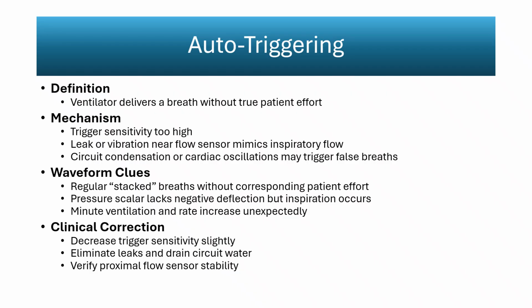Not every irregularity on a ventilator waveform reflects a change in the infant's physiology. Many come from environmental or equipment-related factors, and recognizing these artifacts prevents unnecessary interventions. Water in the circuit is one of the most frequent causes. As water oscillates within the tubing, it generates repetitive rhythmic distortions on the flow scalar. These oscillations have no relationship to the infant's breathing pattern, but they can mimic airway obstruction or erratic effort if not recognized. A circuit disconnection or drifting sensor produces flattened or erratic traces.